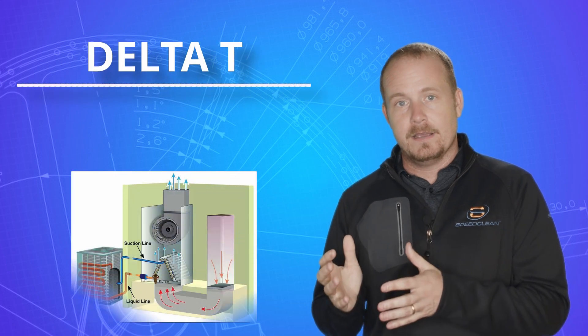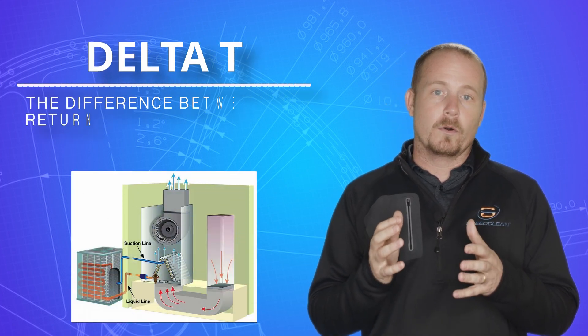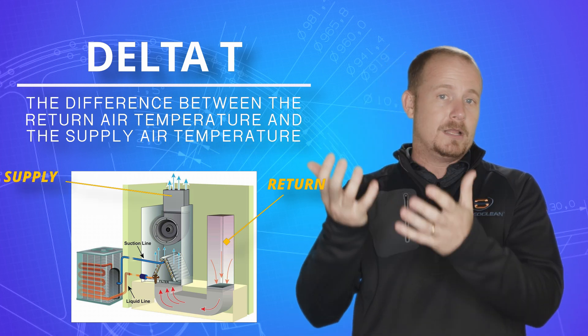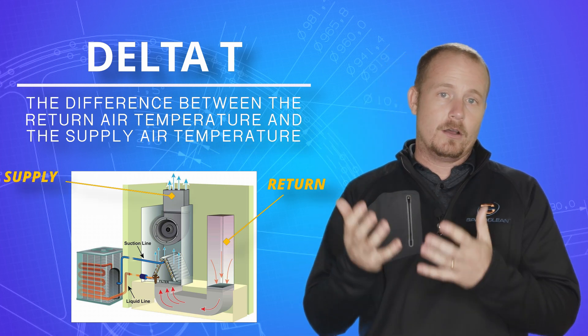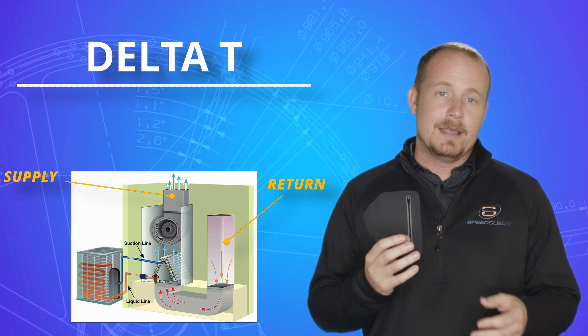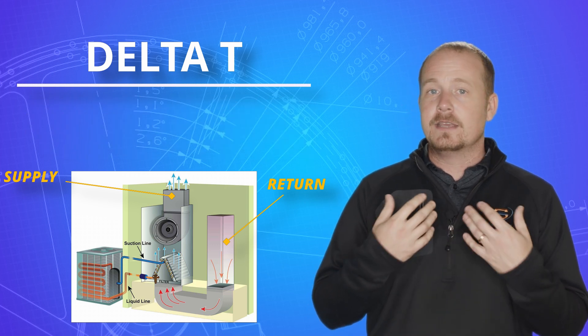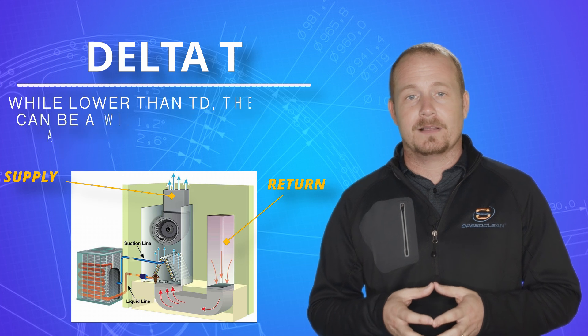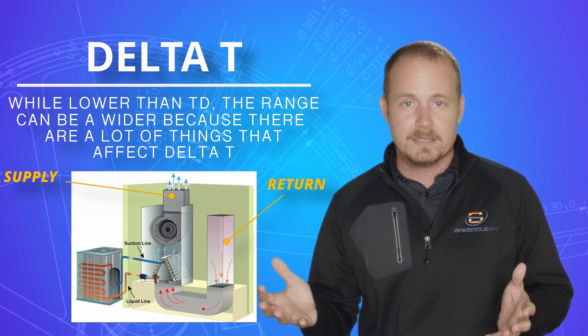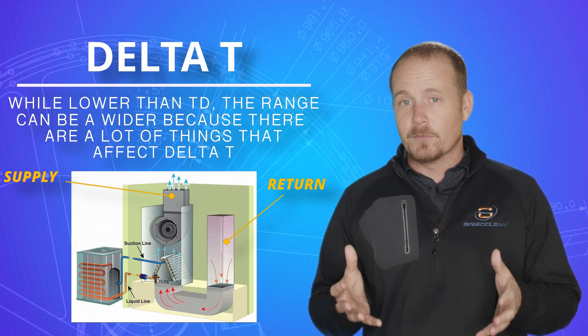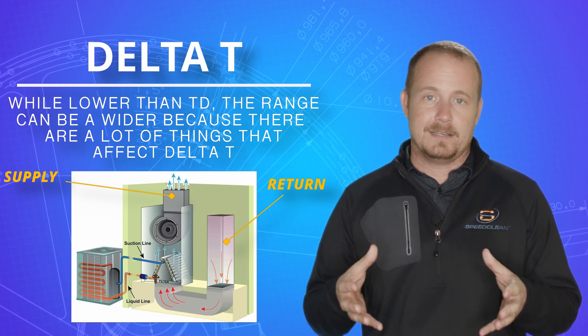Delta T is the term that we use for the difference between the return air temperature and the supply air temperature. And obviously that's going to be lower. Now, I could give you a delta T that a lot of people repeat. They'll say something like between 16 and 22 degrees. It's a pretty big range because there are a lot of things that affect delta T.